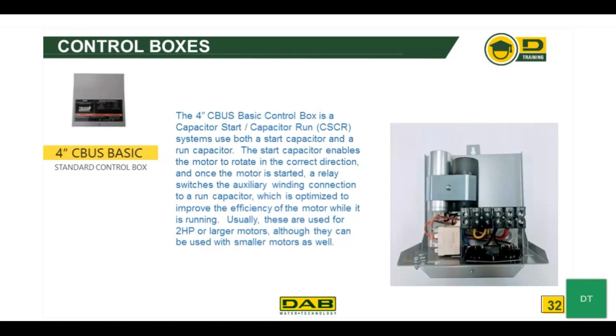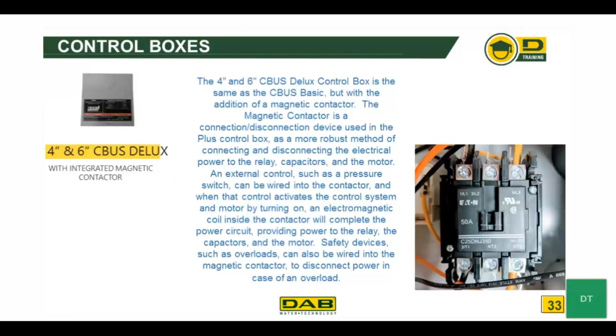This is the 4-inch CBUS basic standard control box. The 4-inch CBUS basic control box is a capacitor start or capacitor run box, CSCR. These systems use both a start capacitor and a run capacitor. The start capacitor enables the motor to rotate in the correct direction, and once the motor is started, a relay switches the auxiliary winding connection to a run capacitor, which is optimized to improve the efficiency of the motor while it is running. Usually, these are used for 2 horsepower or larger motors, although they can be used for smaller motors as well.